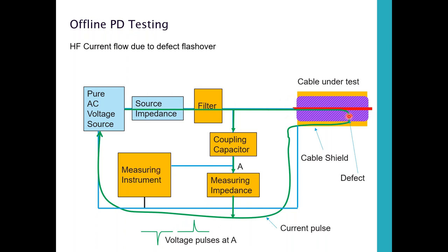If the voltage goes up and there's no problem with the cable, we won't get this current pulse, which is then measured through capacitive coupling as a voltage. We can detect at what voltage this arcing happens. If I apply enough voltage to an insulator, it's going to arc, regardless of what its rating is. If I go enough above it, it's going to start to break down. So you don't want to go that high. You don't want to go 20, 30 times its rating.